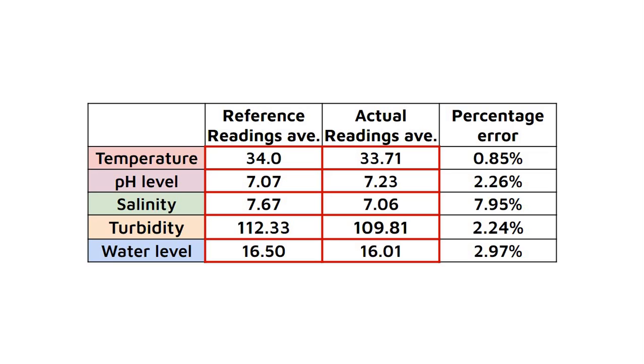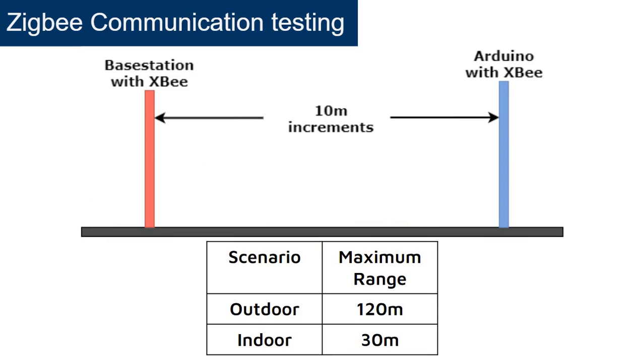Since water level could not be verified through laboratory testing, an analog instrument was used, a steel tape measure. Human error likely contributed to the difference between the readings taken by the sensor and the readings taken from the steel tape measure, which was done through visual observation only. Temperature was also a parameter not verified through a laboratory. An alcohol thermometer was used as reference to compare the readings taken by the sensor. Human error was also expected when taking measurements through the alcohol thermometer, as level indicators were incremented only by quarters, resulting in lesser accuracy.